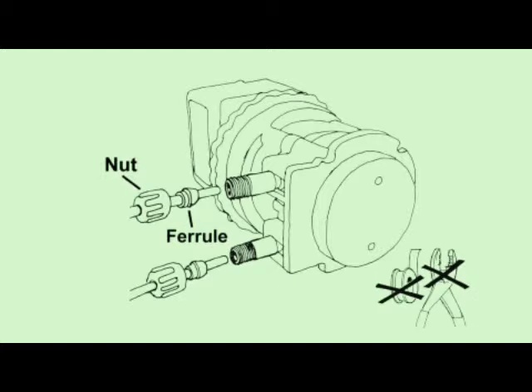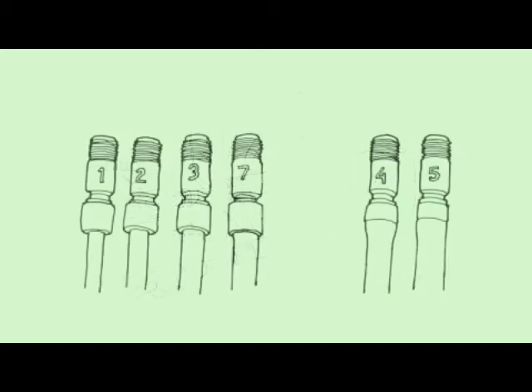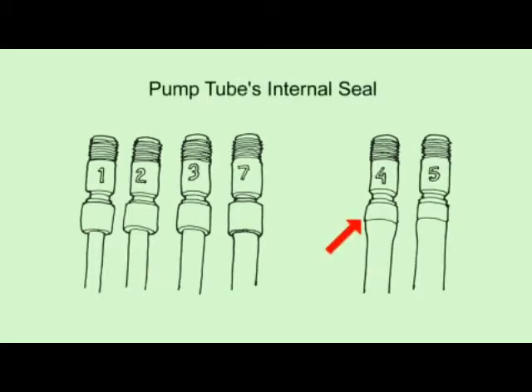Pliers or thread seal tape should not be used because the pump tube fitting is secured to the tube material by an internal seal consisting of a crimped brass collar, and on some of the tubes, the brass collar is under a rubber collar. Using pliers will break the internal seal and cause the tube to leak, and using thread seal tape will interfere with the seat between the connecting nut and ferrule.